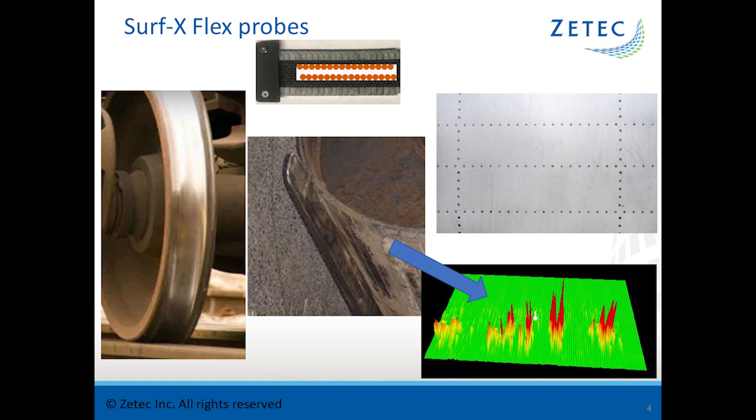The next probe is the flexible probe — the same as the weld probe except without the plus points. This probe was developed for the airline industry for inspecting rivets on airplane skins, but additional applications have been found. One application is train wheels, including the curvature near the end of the wheel. Another is mining drums: large drums about six feet in diameter with significant grooves that can cause cracking. Normally this testing is done with magnetic particle testing, but we pushed the flexible Surf-X array probe down into the groove and saw great indications of the different flaws.